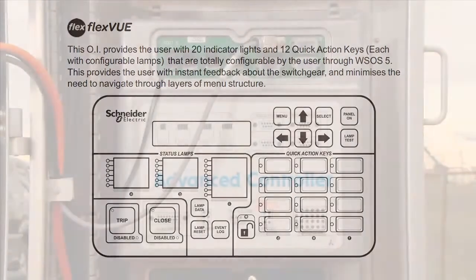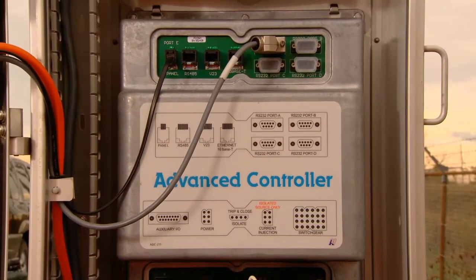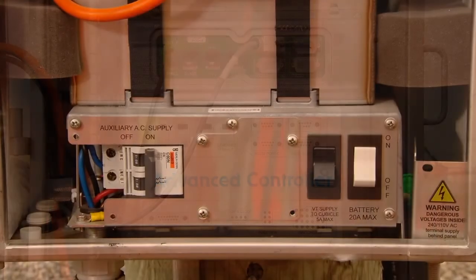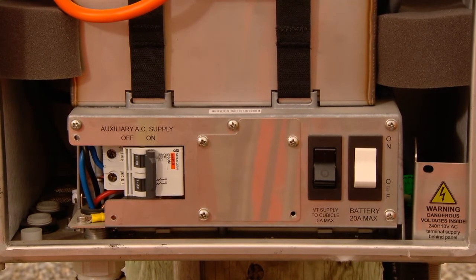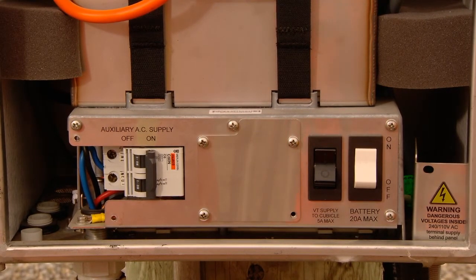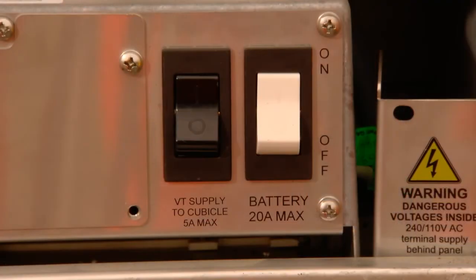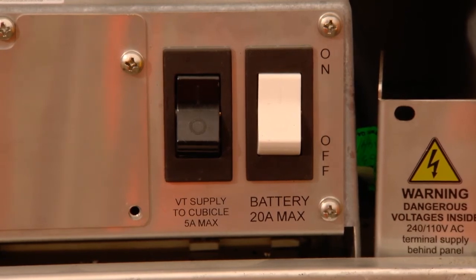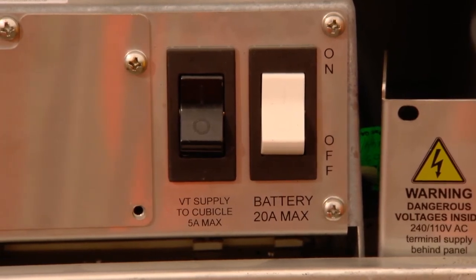At the top of the ADVC processor, you can see the cables that could connect to communications, located in a cabinet space designed for that function. The diagram on the processor cover tells what type of connection is located directly above it. This is a close-up view of the battery, voltage supply, and main breakers. They should all be on while the unit is in operation. As you can see, the cubicle only requires 5 amps to function, even though the battery is capable of delivering up to 20 amps when fully charged.